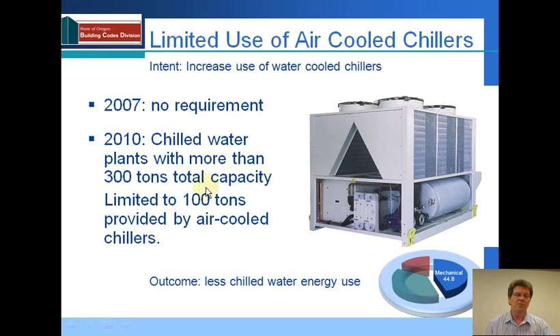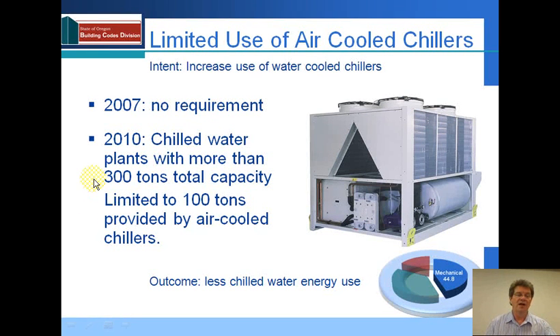Chilled water plants with more than 300 tons of total capacity limit the amount of air-cooled chillers to 100 tons. Often they do want a smaller chiller there as a backup unit. At 301 tons, that requirement exists. Up to 300 tons, it's possible to have a total of 300 tons of air-cooled chillers — just the way that requirement is written.